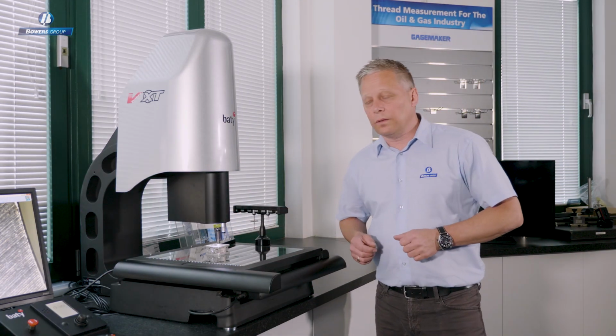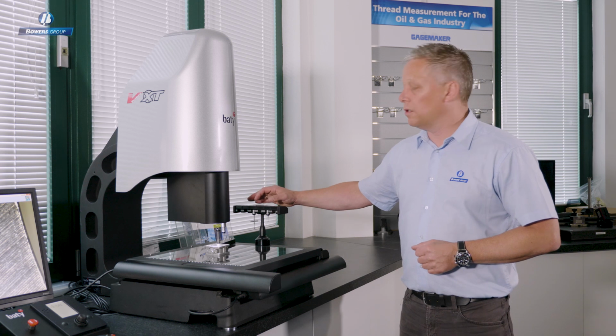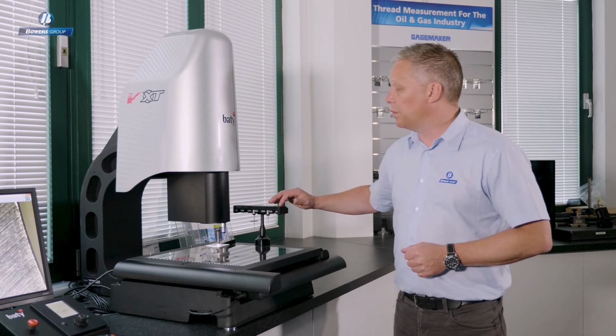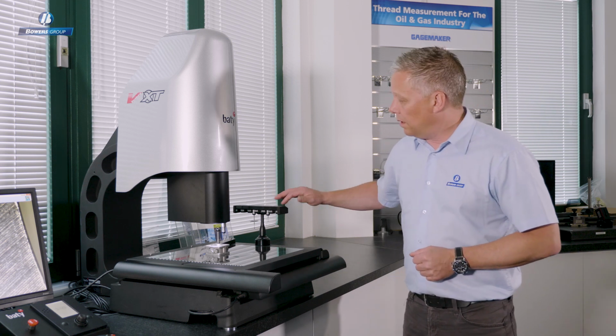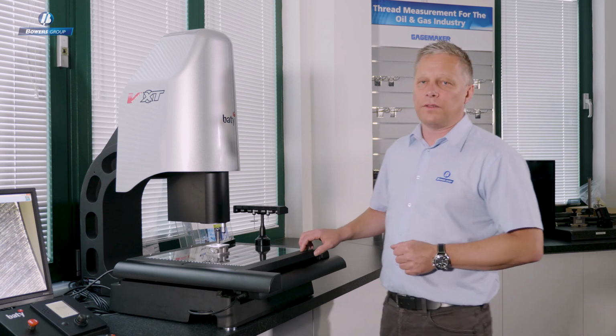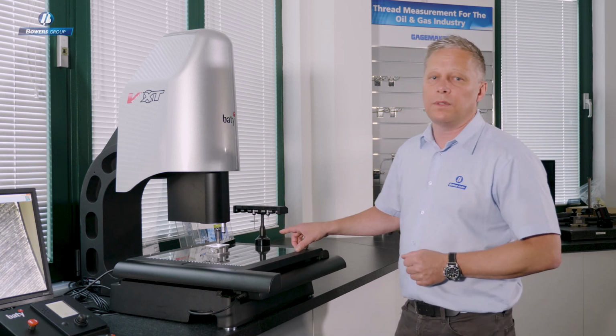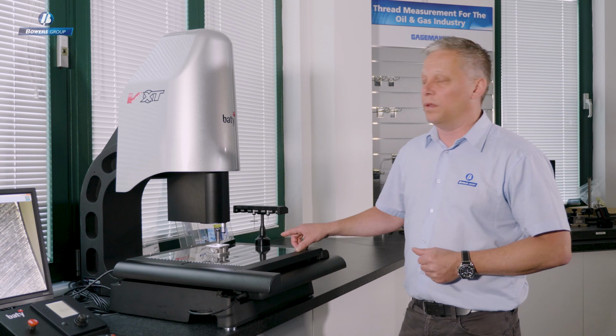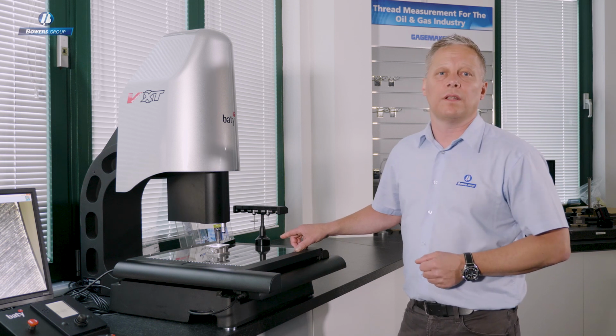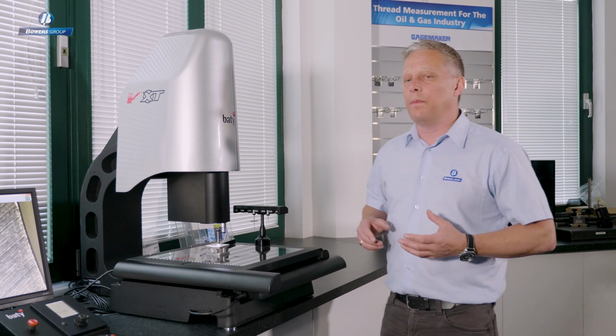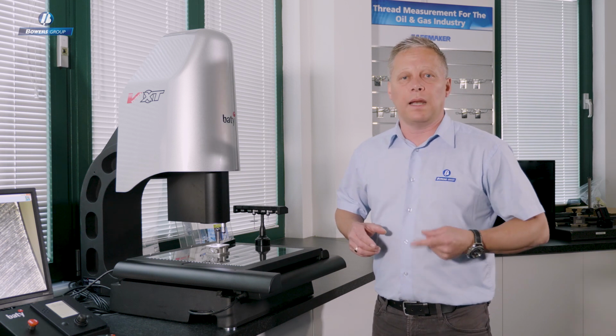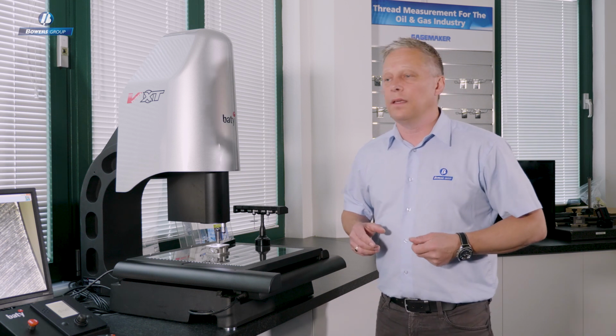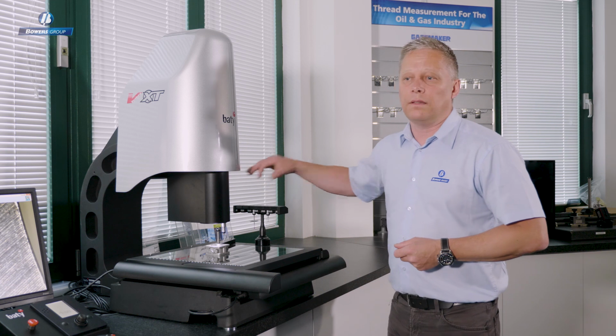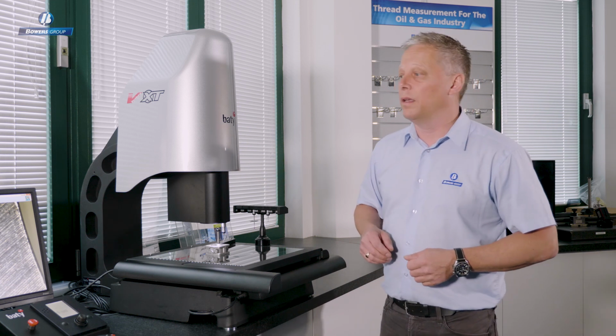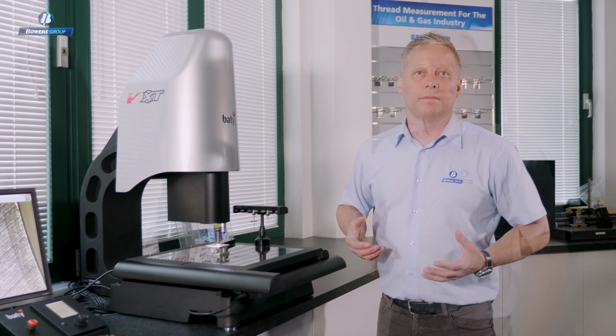So on this particular model, you can see features the optional 6-port Renishaw rack changer. The software allows us to manage multiple probes, modules, and with each module we can have a multiple stylus setup. The software is capable of understanding the calibration status of all of these styli and managing the positions of the styli without any operator influence.